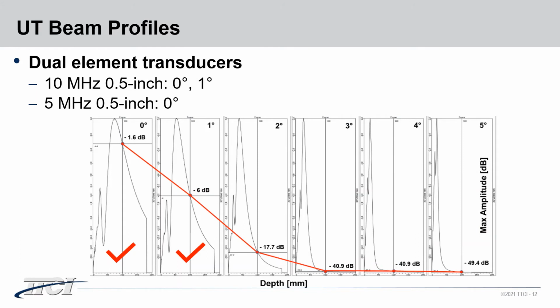For the dual element transducers, the roof angle is a key parameter. The roof angles varied from 0 to 5 degrees in the simulation. The plot in this slide shows the simulation results from a 10 MHz half-inch dual element transducer. As we can see, the smaller the roof angle is, the higher the signal amplitude is. The transducer with 0 roof angle generated the best signal of all 6 cases. 1 degree roof angle was acceptable as well.